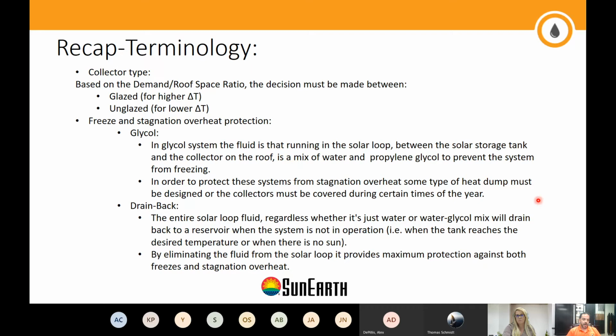Another aspect that you want to take into consideration when designing the system, obviously we talked about it, is how much space you have for the array and how many banks of collectors you can fit into the space available. Stuff that comes up is the number of collectors that you can put into a bank. There is a limitation on that based on thermal expansion. Once the collectors start heating up, the system starts heating up, it will expand, and that has to be taken into account. Also, the interruptions in the flow rate is another important aspect to always be mindful of, depending on the size of the header that you're using in your collector, and the sizes that are used in the main pipes for the building. So that has to be taken into account.